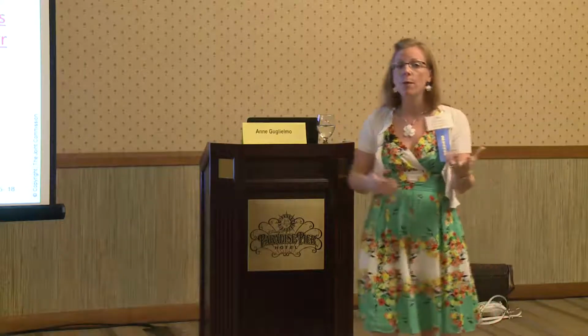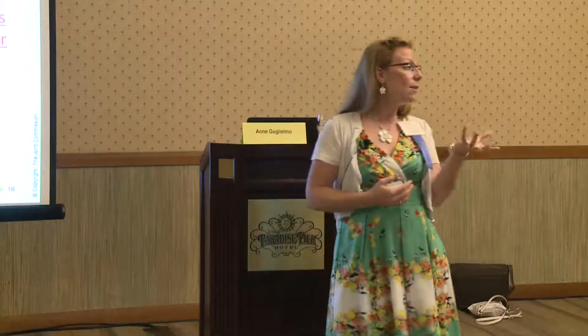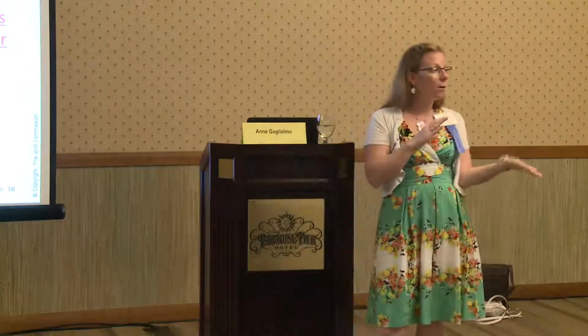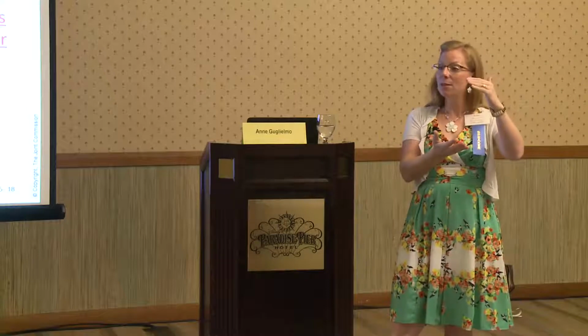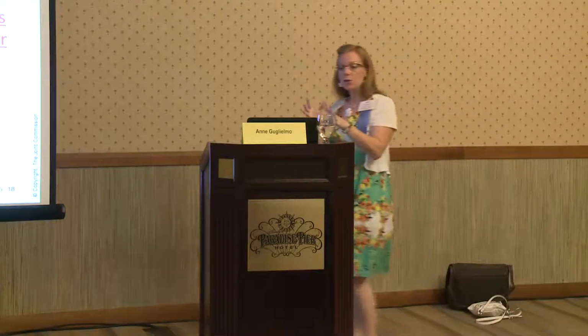At EP number 3, what we've done here is change how we classify. For the longest time, we had life support equipment and non-life support equipment. So people would come to me and say, hey, Ann, is a generator really life support equipment? Well, the generator itself wasn't life support equipment, but it provided the essential power to the life support equipment, so we always lumped it under life support. Now we've changed the view to high risk versus non-high risk, and your life support items fall under high risk, obviously. But I can have a generator, which is a high-risk item if it fails, and I don't have to call it life support when it's not truly supporting life. Does that make sense? That was where the shift was.